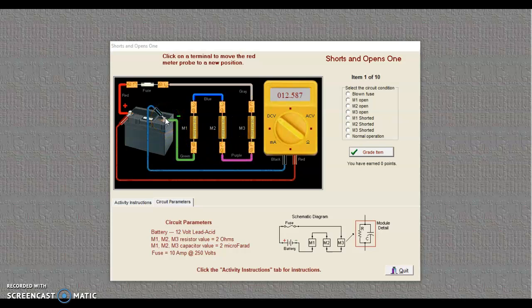In this case, our negative probe on our meter is going to stay put. And so we're going to isolate and narrow what's between the probes. So let's begin moving the probe around. We do not have to go to this terminal because the red wire is not one of our possibilities here. So let's get on the other side of the fuse and see what happens.